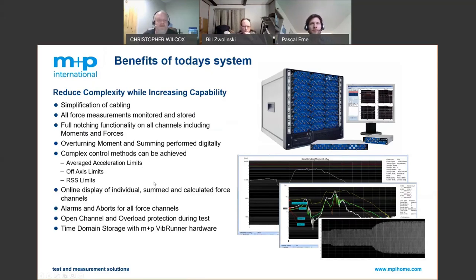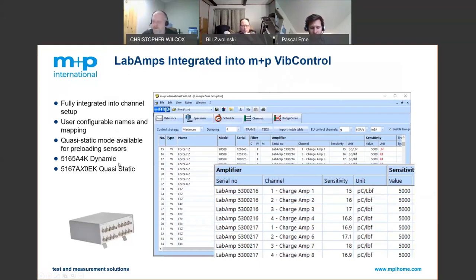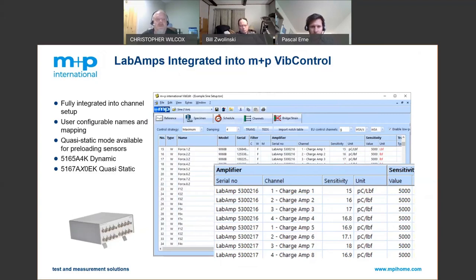In 2019 a customer came to us looking for an all-in-one solution. We chose the Kistler Lab Amps because they offered quasi-static mode, had the most experience in force limiting, and the quasi-static mode with very high dynamic range allows preloading on the Z-axis vertical compression. They also offer the same model in a dynamic mode, which helps with cost. Since all sensitivities and ranges are set within the software, they are stored with the result file, allowing traceability.